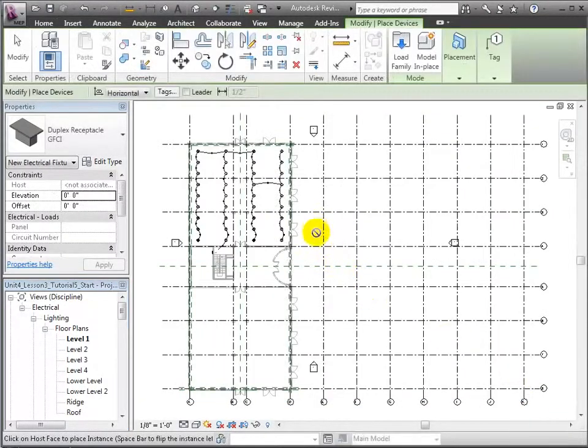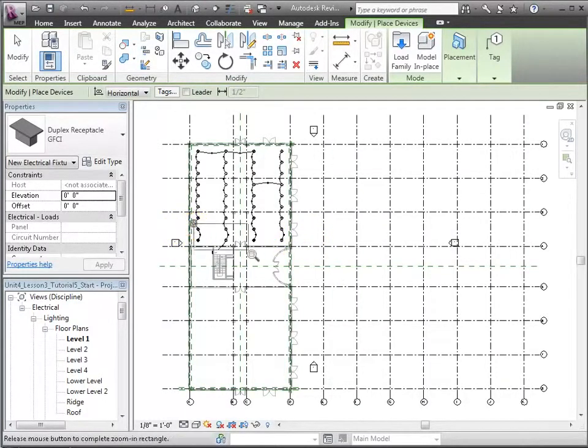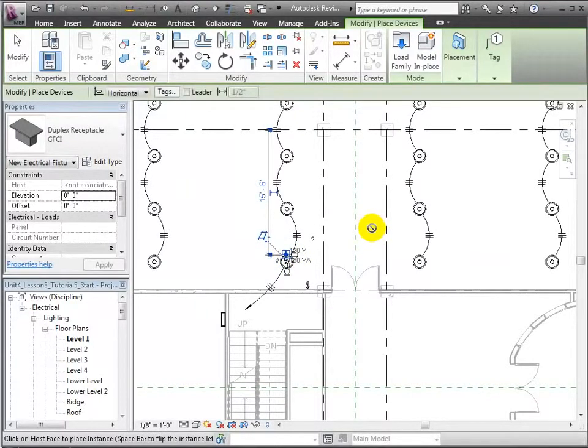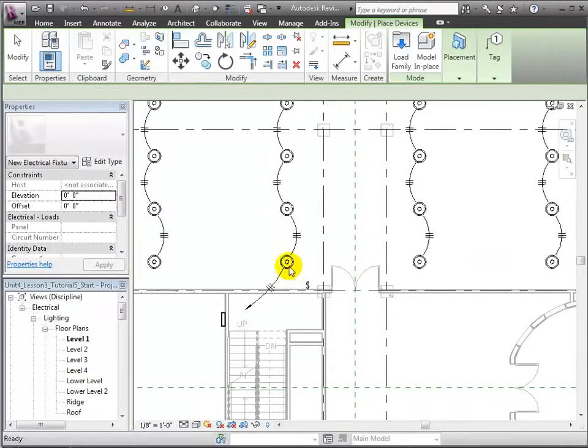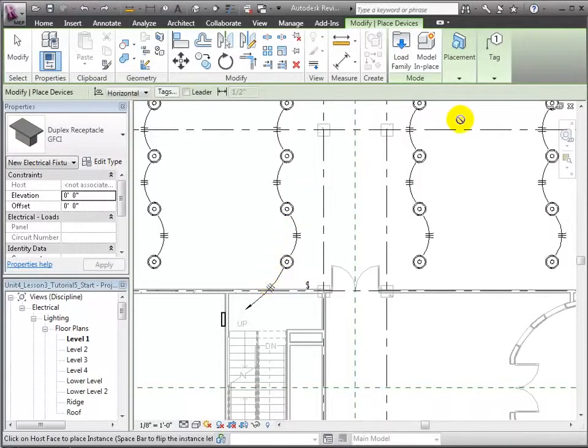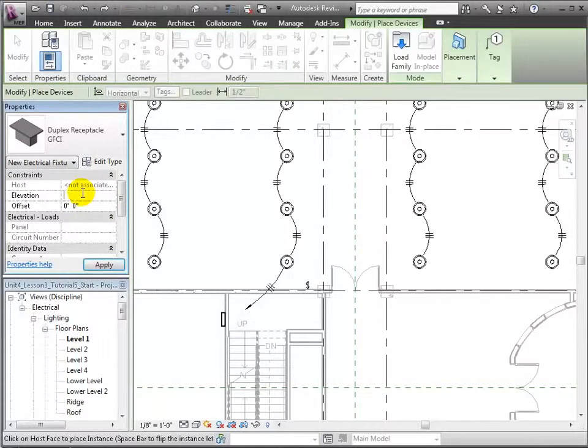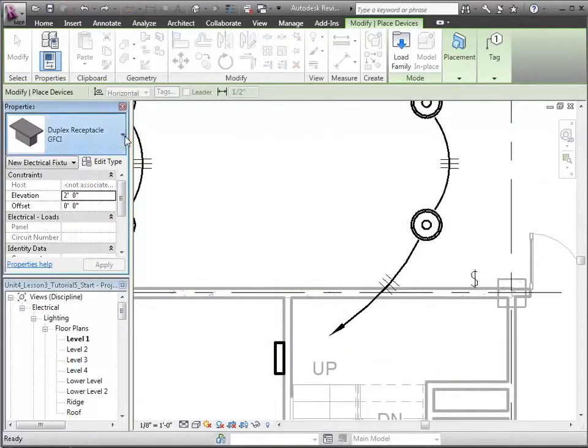Let's zoom in on the wall near the entry and we'll use the Place on Vertical Face option. Let's set the elevation to 2 feet for a special need. This is a bit higher than the 18-inch elevation typical for most standard wall receptacles.